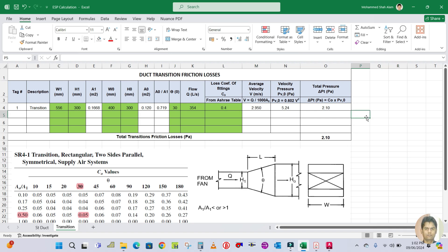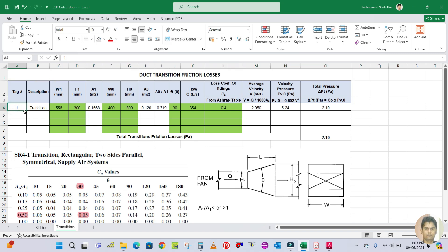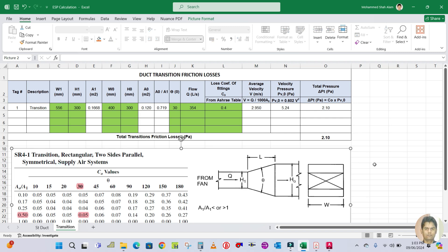First of all, I have prepared one Excel sheet here - this is the duct transition friction loss calculation Excel sheet. The first column is the tag number and the second column is the description for the piece. The width one and height one values are taken from the ASHRAE handbook.